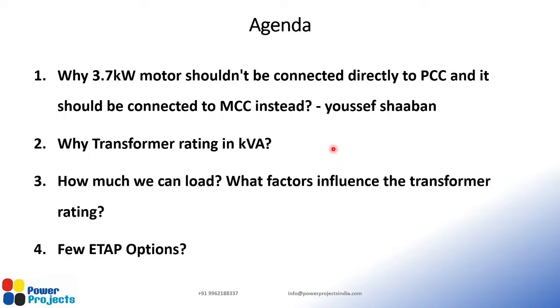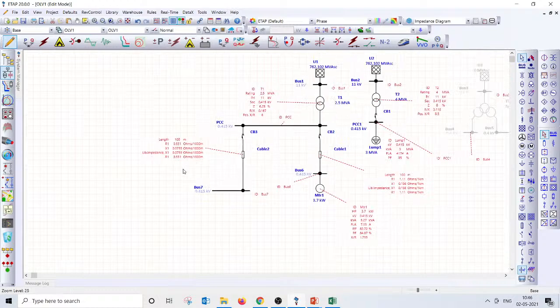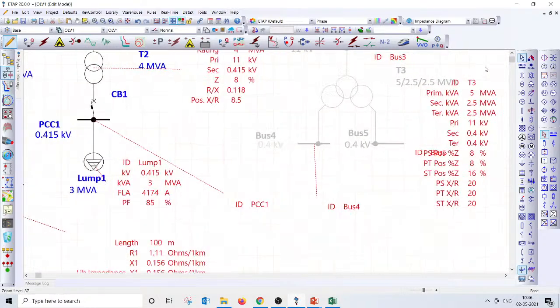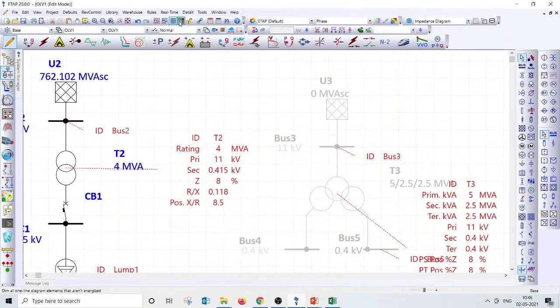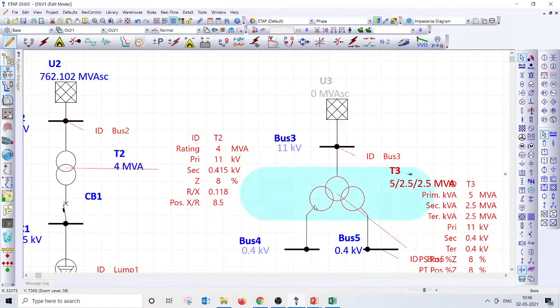And Arun Kumar asks: in a three winding transformer, a fault in two windings will impact the power supply and the third winding. Could you please elaborate on this? I guess that's a simple, straightforward answer. We have seen an image here. If there is a fault in any one of the windings, then you cannot really operate this transformer.